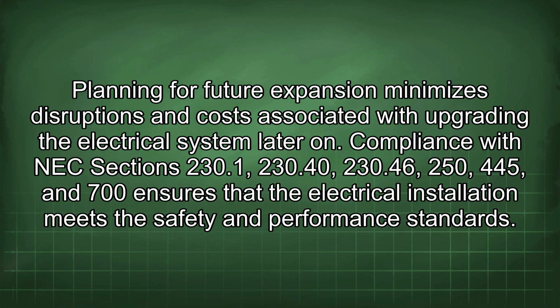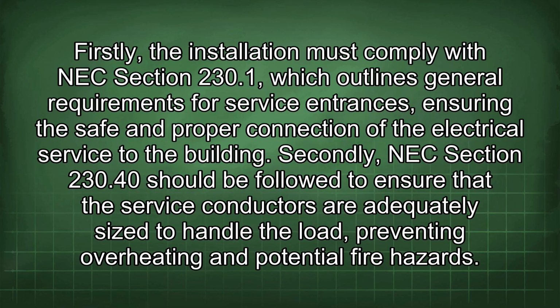Planning for future expansion minimizes disruptions and costs associated with upgrading the electrical system later on. Compliance with NEC sections 230.1, 230.40, 230.46, 250, 445, and 700 ensures that the electrical installation meets the safety and performance standards. Firstly, the installation must comply with NEC section 230.1, which outlines general requirements for service entrances, ensuring the safe and proper connection of the electrical service to the building.